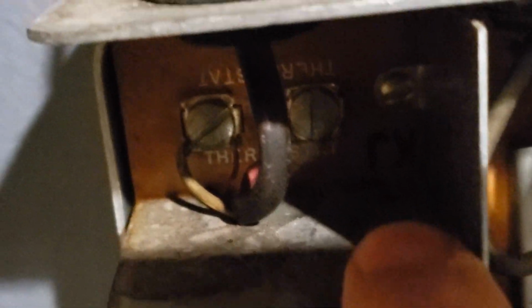I mean, surely you can figure out that the 2 wires going to the thermostat here are going to be W and RH. But where's the common wire? I thought it might have been here, and I had a mock-up where I had 3 wires coming out, and I had it go to the Ecobee, and this is basically chassis ground. But it didn't like that.